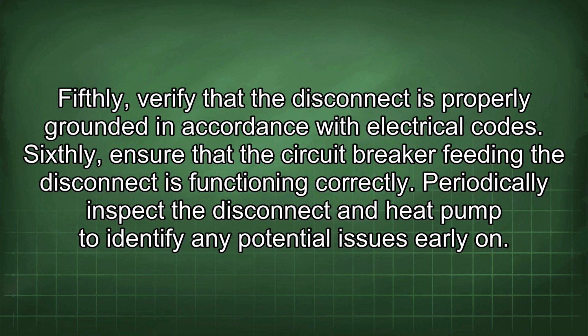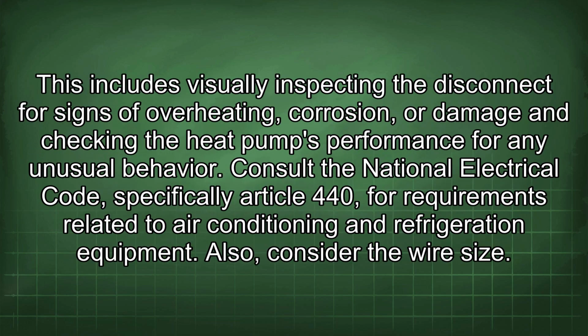Periodically inspect the disconnect and heat pump to identify any potential issues early on. This includes visually inspecting the disconnect for signs of overheating, corrosion, or damage and checking the heat pump's performance for any unusual behavior. Consult the National Electrical Code, specifically Article 440, for requirements related to air conditioning and refrigeration equipment.